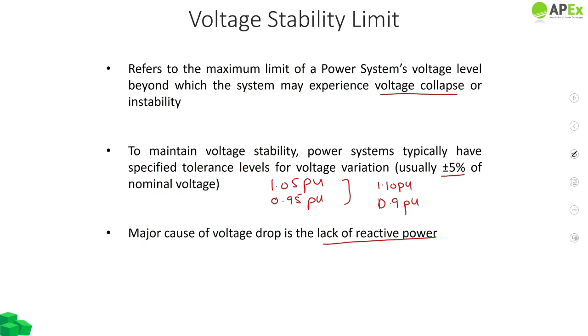Okay, but what causes this drop in the voltage? Basically, it's the lack of reactive power. We discussed previously that inductive loads require reactive power. The lines that are loaded beyond their surge impedance loading also consume, or require, reactive power. If we do not provide enough regulation through our generators or devices like capacitors, SVCs, STATCOMs, etc., then the receiving end voltage drops to a point where no further power could be transmitted and the voltage falls below the required levels.